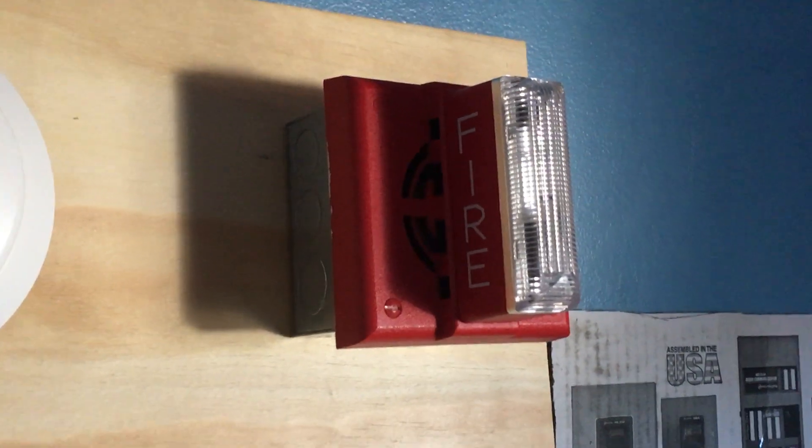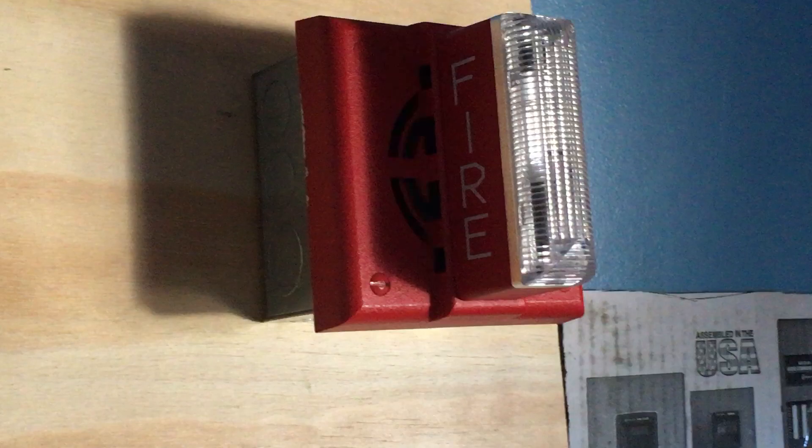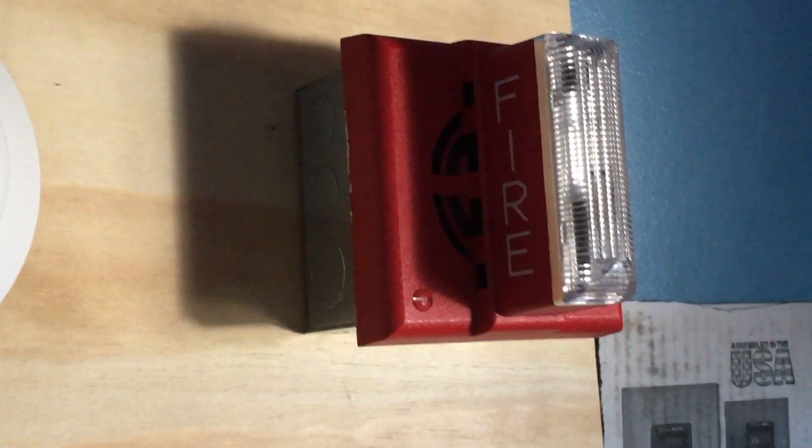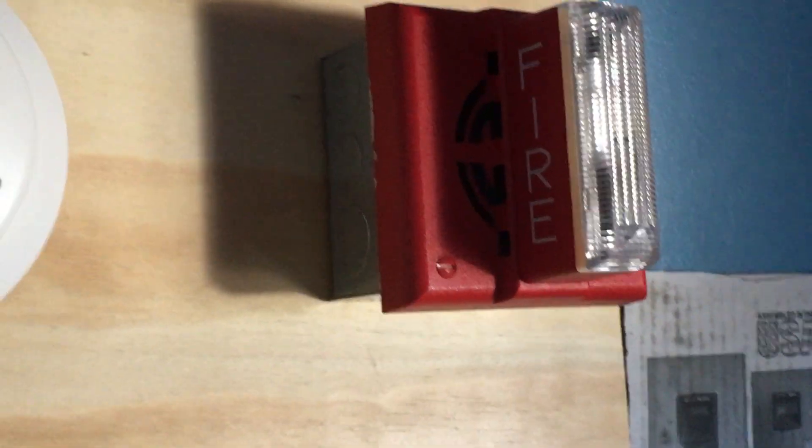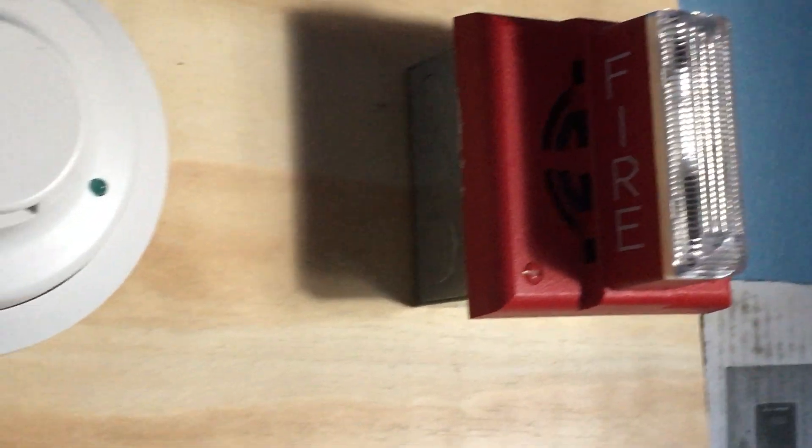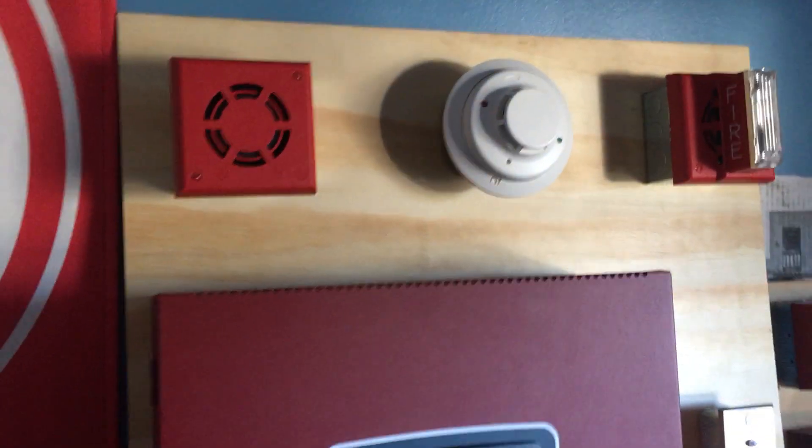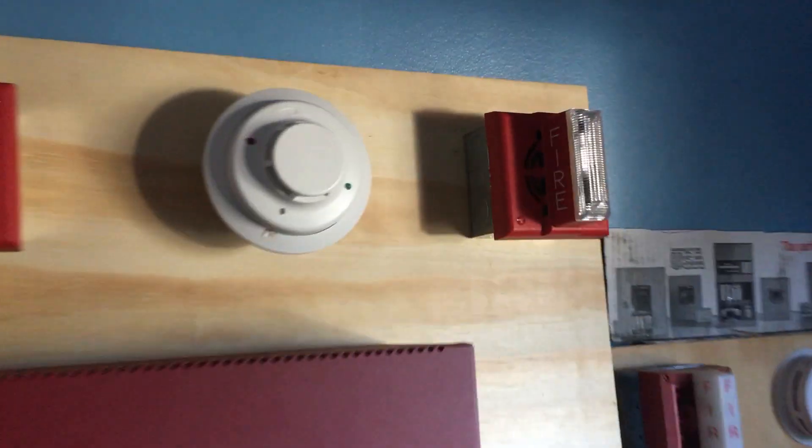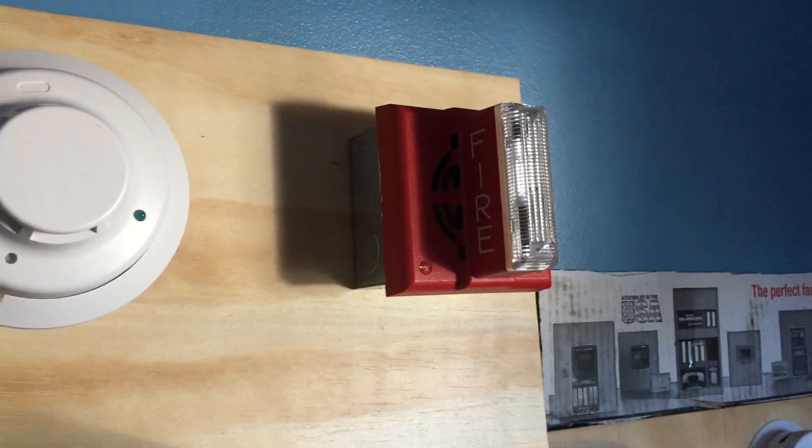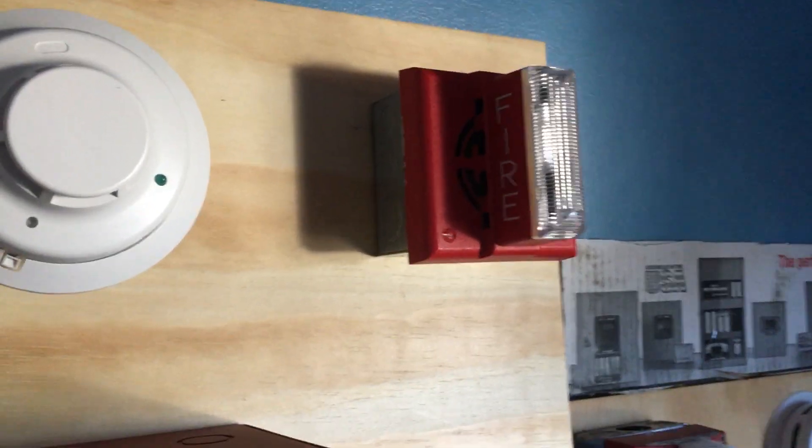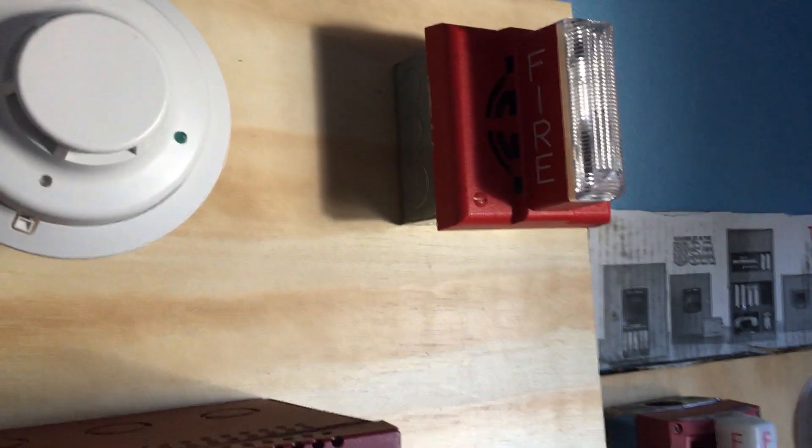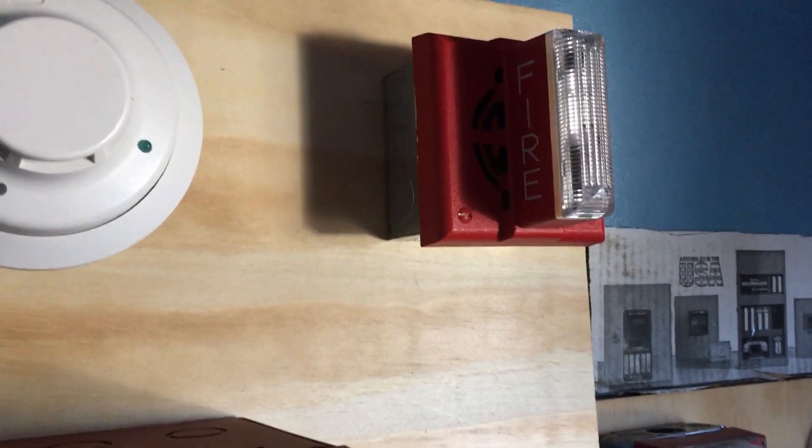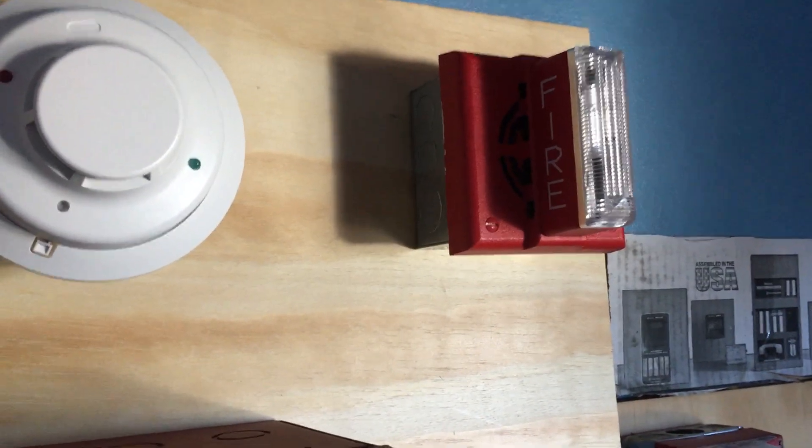Fun fact, both of these are steady, but for whatever reason the Gentex SHG is coding itself to code 3. I think it's because of the jumpers on the back. I'm not sure why it's not receiving the panel coding. This one is, but who knows.